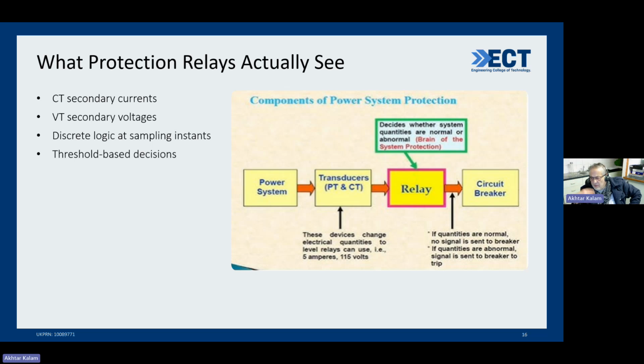And then there are some logics over there, if you want to have an impedance, voltage over current. If you want to talk about overcurrent, you have a threshold of, say, 5 amps, and over that is overcurrent. Exactly in the same manner, overvoltage, all these types of differential relays, directional relays and distance relays, you name it. As I told you, when I talked about overcurrent, if the current goes more than 5 amps, 15 amps, whatever you decide as your threshold, that is the basis for your decision. So the relay only sees a representation of reality, not the reality itself, my friends. You see this diagram that I've got. Here's the power system, here are all the CTs and the VTs, and this is the relay. The relay sends the signal for the circuit breaker to operate. The work is being done by this guy, the circuit breaker.